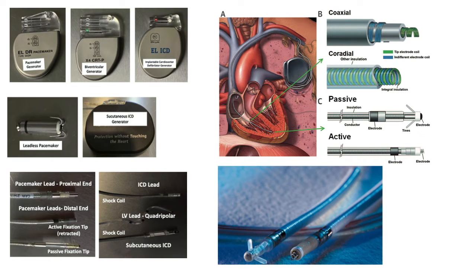The generator is connected to the myocardial tissue by the pacemaker lead, and this lead contains conductor coils. These coils are separated by an insulation material. The design of the coils in the leads is either of two types: coaxial, meaning that there is a coil inside a coil, or co-radial, meaning that the two coils are arranged side by side. The tips of the leads have a variety of designs, and sometimes they are porous. Why? To improve the surface area of contact with the endocardium, minimize the development of inflammation and fibrous tissue, which would increase the pacing threshold later on.